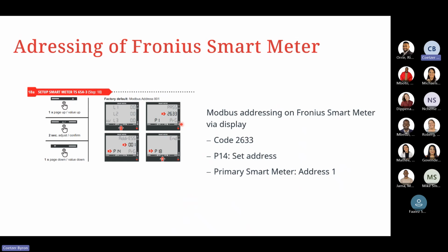If we want to make use of multi-smart metering, we'll need to change the address. What we'll do is hold the adjust confirm button, and this will allow us to get into the meter. We will then hold or enter the code 2633. This will allow us to change that Modbus address number. Once we are happy, we simply close out once we've reached page 18 on the meter itself.